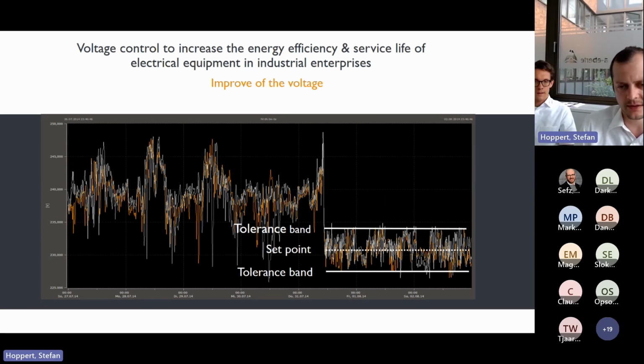But just before I make this example, I will introduce you to the operation principle, what the system is doing. It's easily explained. The system takes the left unbalanced and fluctuating voltage and brings it to the right voltage according to a reference value in tolerance limits. The tolerance limits and also the set point are adjustable because these are parameters, and that's the job of the system. The system brings it back to a really soft and good voltage range which can be adjusted.